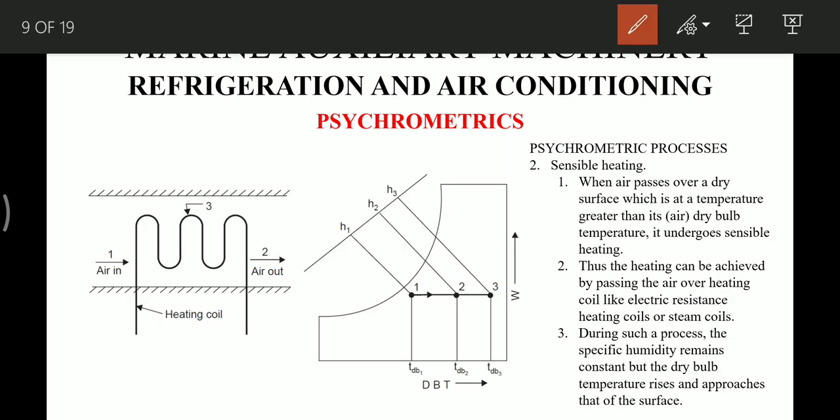The next process is sensible heating. As air passes over a heating coil and moves out, it gains temperature. This is represented by a horizontal line moving right on the psychrometric chart, and from these points we can find the enthalpy change. When air passes over a dry surface at a temperature greater than its dry bulb temperature, it undergoes sensible heating. Sensible heating can be achieved by passing air over a heating coil such as an electric resistance heating coil or a steam coil. During this process, the specific humidity remains constant but the dry bulb temperature rises toward that of the surface.